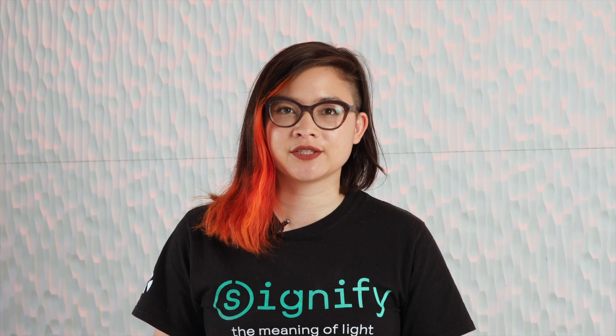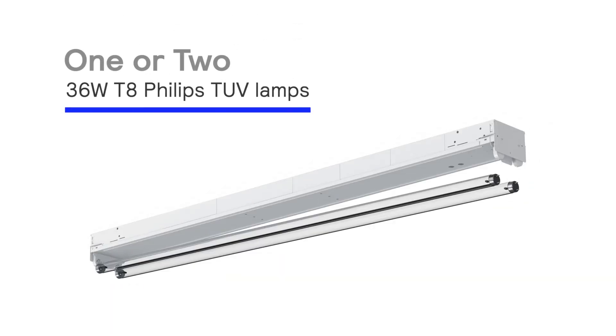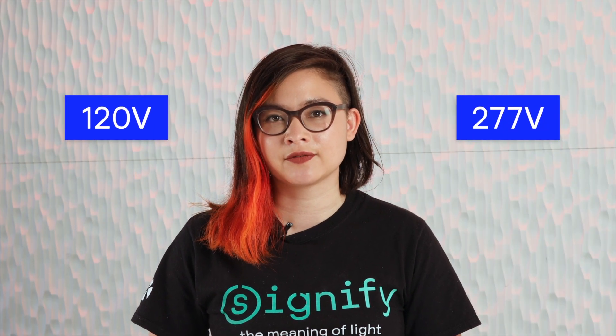The Alco germicidal UV strip offers a layer of direct disinfection on objects and space purification. The four-foot strip is available in a one or two lamp configuration that utilizes the 36-watt T8 Philips TUV lamps and operates from 120 to 277 volts.